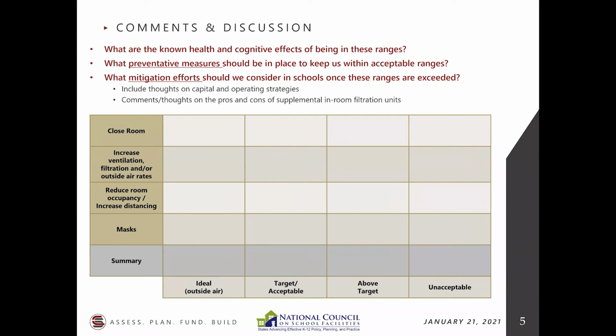Wholesale though, Bob, I would say, and to all of you, buying an air cleaner is not a bad thing. It is a supplemental approach. We all know that. It's not a primary replacement for ventilation. And remember, I think they are very applicable in classrooms where you have limited amounts of ventilation that you could bring in. But across the board, to put them in every classroom in a school, you're not only going to have an initial cost, you're going to have a replacement cost that is significant related to the filters. Those filters typically need to be changed out every 6 months to a year. In a heavily densely occupied classroom, you may be closer to having to change it out every 6 months. So, it's really helpful information.